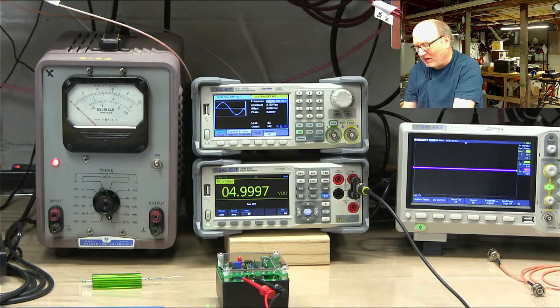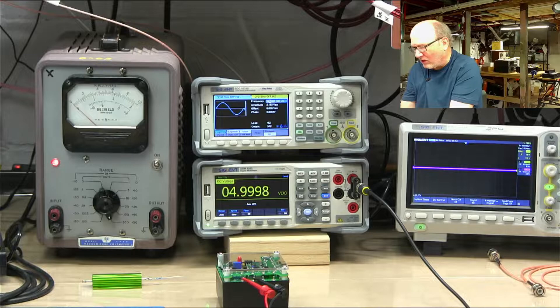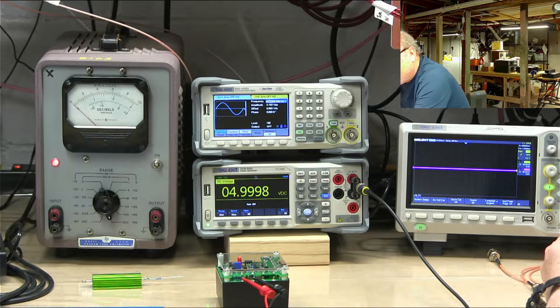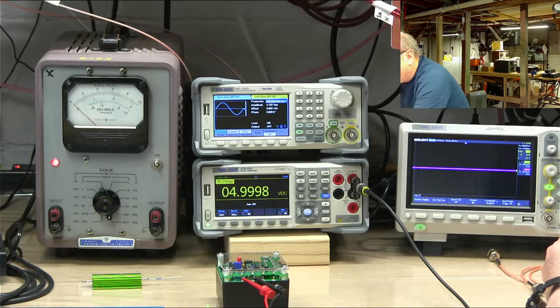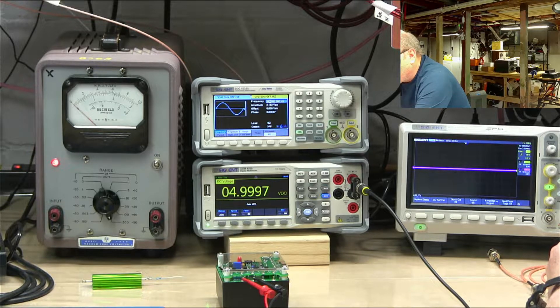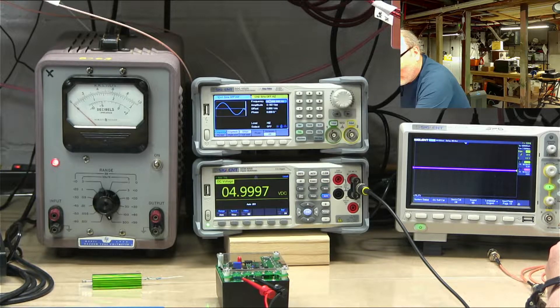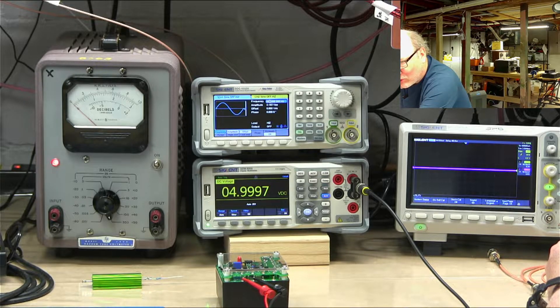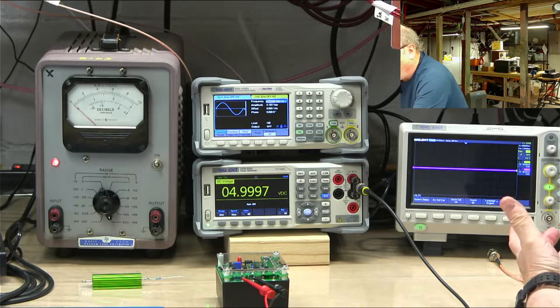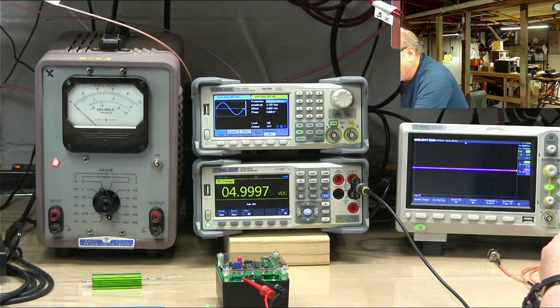The calculated tolerance of the meter in DC mode was plus minus 0.00155, and we are reading about 0.0003 off, so we're well in tolerance.